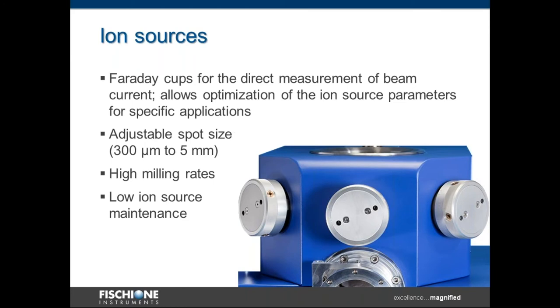Faraday cups are utilized for the direct measurement of beam current. This allows the ion source parameters to be optimized for specific applications. Additional key features include the ability to adjust the spot size anywhere from about 300 microns up to 5 millimeters. High milling rates combined with low ion source maintenance make this an ideal instrument.